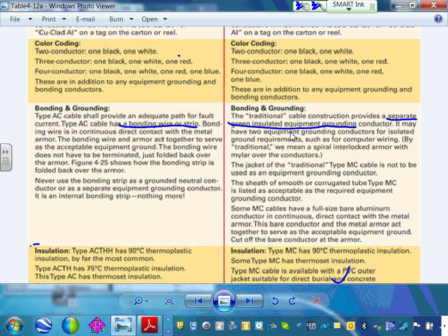And what you do, guys, typically you cut this one and you put the right fitting on it. You're not even supposed to bend it this way. You cut it and you put a bonding fitting. This guy, you just chop it, you put the right fitting on it. You don't tie it to anything. And the shield of the cable, as well as that wire and the connector, act as your equipment grounding conductor. For this guy, the main equipment ground conductor will be going through the insulated one, and this also will give you some redundant equipment ground conductor. Am I making sense? So this guy, it goes directly into the box.